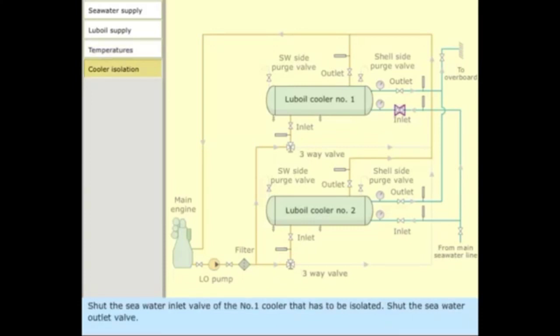Shut the sea water inlet valve of the number 1 cooler that has to be isolated. Shut the sea water outlet valve. Divert the lube oil flow by adjusting the 3-way valve. Shut the lube oil inlet valve. Shut the lube oil outlet valve. Adjust the 3-way valve back to the normal position.